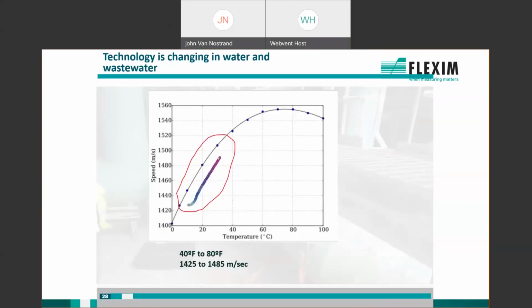So whenever we start the meter up, we verify that the meter is set up properly by measuring that sound speed that I mentioned earlier and ensure that it matches what we would expect it to be. So in this case, with that very accurate sound speed measurement, what you're seeing on the screen here is a correlation of a particular chemical versus the sound speed. This is a sodium hypochlorite application, which has a sound speed, as you notice on the bottom, from 1425 to 1485 meters per second. So we'll set this up and we can calculate the concentration of sodium hypochlorite in this application.